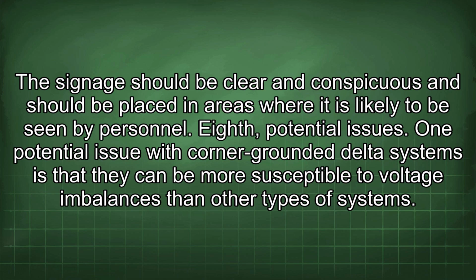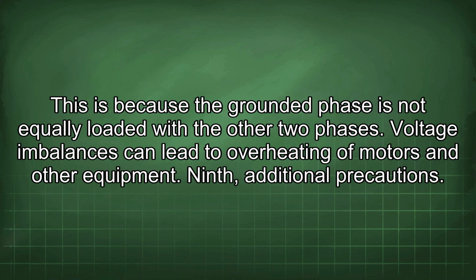8. Potential issues. One potential issue with corner-grounded delta systems is that they can be more susceptible to voltage imbalances than other types of systems. This is because the grounded phase is not equally loaded with the other two phases. Voltage imbalances can lead to overheating of motors and other equipment.